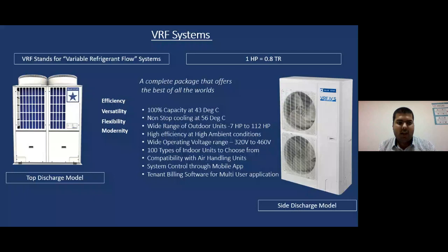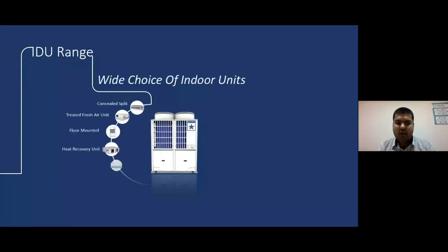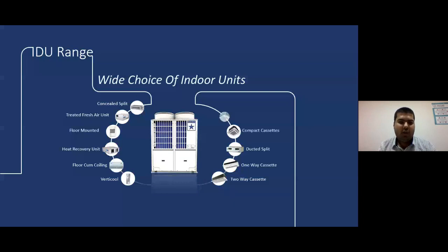So this is the basic IDU range which a VRF can handle, starting from concealed splits, treated fresh air units, floor mounted heat recovery units. It goes up to anything you name in the air conditioning field. There are basic normal units like high wall and large cassettes, but I want to highlight 2 points: a one-way cassette unit and a two-way cassette unit, which you can see here. These are units which we can install only with VRF, and one-way cassettes look very nice for room applications. Suppose you don't want to install a high wall machine on the wall, you can very well install a one-way cassette AC in the ceiling as well. If it is a one-way, you can install it in one corner. If it is a two-way cassette, you can install it in the middle and all the areas can be used.